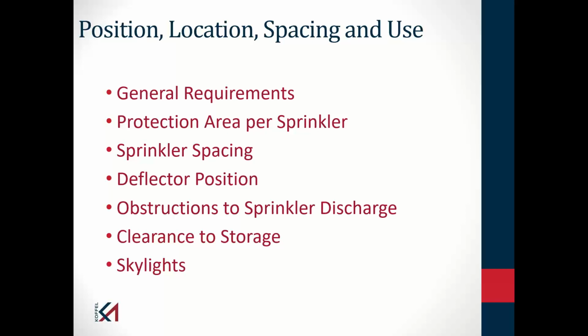What happens in a fire is the plume goes up to the ceiling. We develop a ceiling jet and a hot layer in the top of the room. So unless the fire plume is underneath that metal pan, the hot gases are still going to go to the ceiling, and that means we're going to have a delayed time to operation of the sprinkler. There are a variety of obstruction rules with the basic intent that we have to get water to the other side of this obstruction.